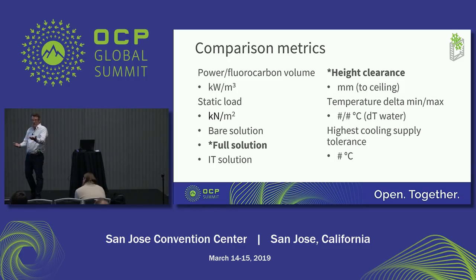Yeah, that's one of the strategies of manipulating the delta. In this case, the delta can be relevant for heat rejection for the dielectric liquid. If we look at the common design specs for the Asperitas technology, for example, our heat exchangers work most optimally with a delta of 10 degrees Celsius. That's what they're designed for. Then they have their best optimal efficiency, both on delta for the facility. Lower delta will always work, but then at some point it will require higher flow rates. But a higher delta, and we manipulate the delta with valves automatically, because we're thermally optimized.